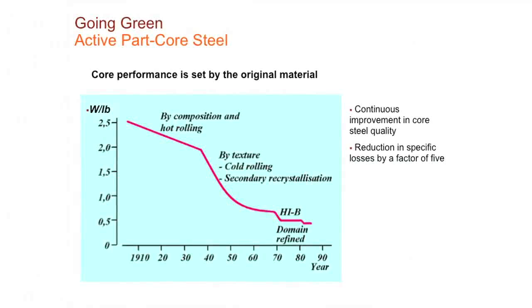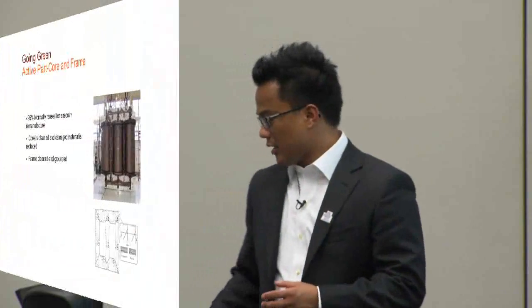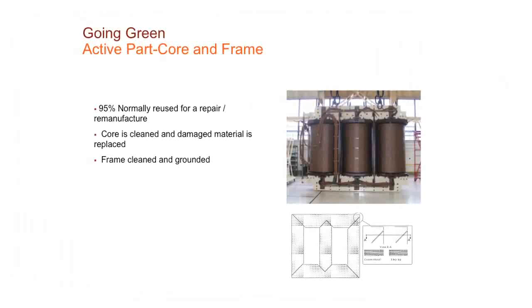The second item typically is the core. In the past several years, from 1910 to 1970, there was a significant improvement in the core loss, the specific losses. But from 1970 on, we haven't seen really that much change in the specific losses in the core. So therefore, many times we can reuse the core of the transformer as long as there's not major failures or major problems with the core. Most of the time, I'd say about 95% of the cases, we are able to reuse the core.